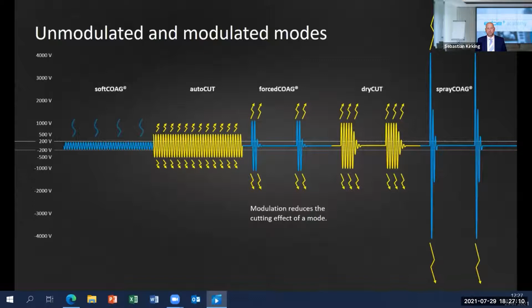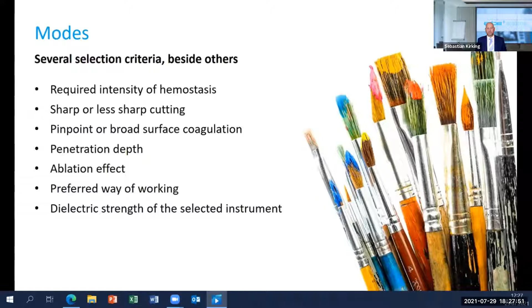You can select from these modes depending on the required hemostatic effect or the cut sharpness, or if it shall be rather pinpointed or have a broader and more superficial coagulation effect, or on the contrary, a rather deep and ablating effect. But it can also simply depend on your preferred way of work. Depending on the electrosurgical unit, there can be several options. A technical limitation, though, comes from the maximum voltage that the instrument and its insulation can tolerate. This is an advantage of monopolar instruments, as they can be used with much higher voltage than bipolar instruments.